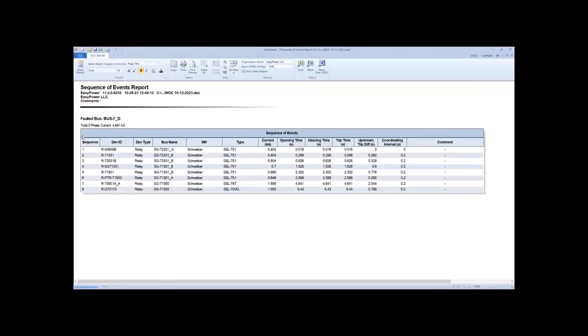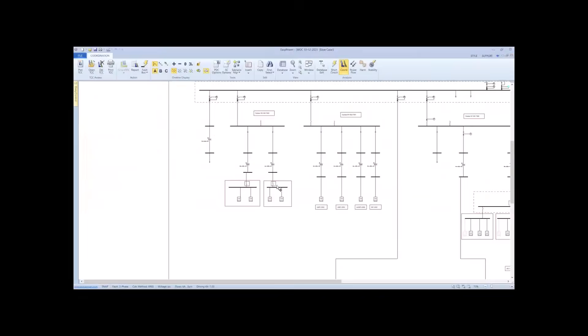So let's confirm using the sequence of events report. This is very useful - we can simulate a fault everywhere, select the sequence of events, and see how each protection upstream works, and the times, and so on. I made sequence of events on three different cases to confirm that in all cases the sequence of event is correct, therefore the settings of each relay are okay. This is something very nice about sequence of events.